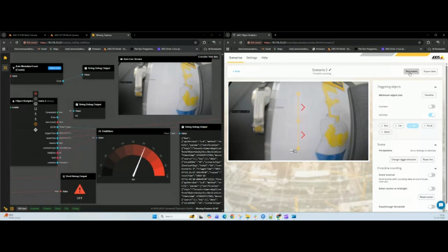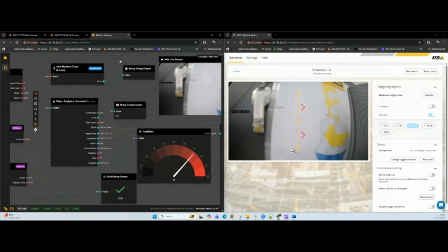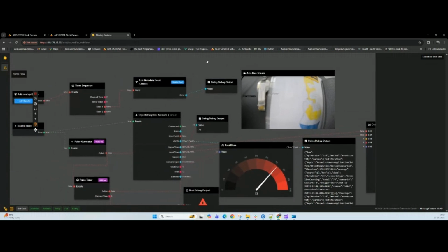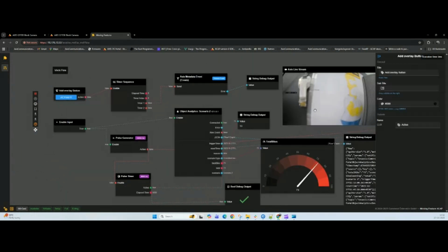So what about TOF, timer off delay? TOF is the exact opposite. It gives you a coast or a hold period after the trigger is gone. How does that work? The output goes true instantly when it's enabled. But when the enable input drops to false, the output stays true for the set time.